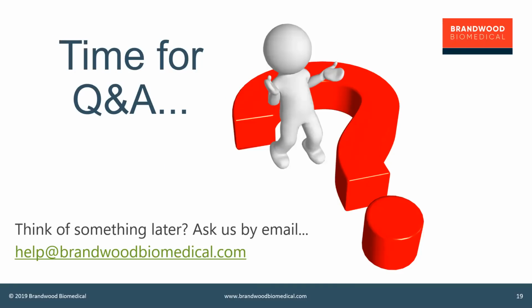We've got only a couple of questions and a few more minutes left before we wrap up. One question, I think you've actually covered this, but is it normal to have different product specifications for USA submissions and a separate one for EU submissions? Realistically, it's not often that you would want to have two product specifications for a product that's going to multiple locations. Normally, if you need to have product specifications that are unique to a geography, you will create a separate product because you need to have a separate model number and you need to be able to show that that product is unique to the other one.